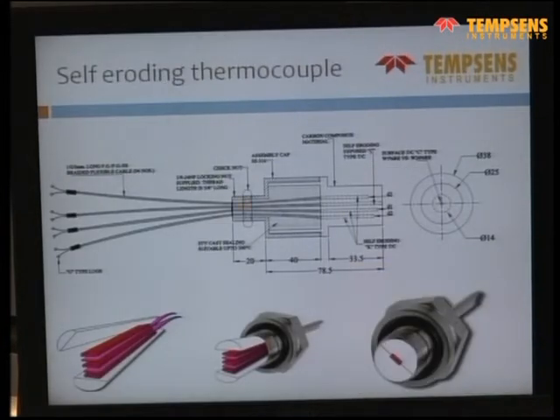We also gave to some customers, like the advanced naval lab, a self-eroding thermocouple. The main advantage of a self-eroding thermocouple is that the response time is in milliseconds, just a few milliseconds. Here, as the thermocouple is burning off, it is still making contact. It has a layer of insulation. The red one is an insulation layer, and the pink one is the thermocouple, one is plus, then the insulation layer and minus. It is sandwiched between two metal parts, and it's just like a small strip.